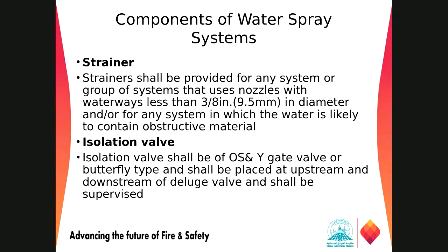Now we come to the component strainer, right? We need a strainer in all the deluge water spray nozzles, because the water spray nozzles are very small compared to our sprinkler system, right? If you remember, in the sprinkler system we need 5.6 K factor, or in another unit we can call it 80. So those nozzle orifice sizes are larger, so we don't have a problem with any kind of obstruction or foreign materials.